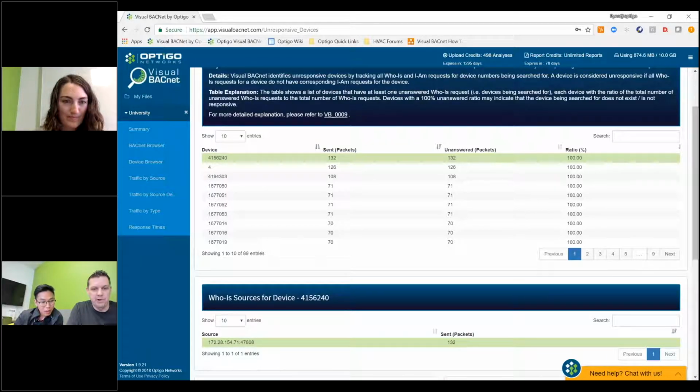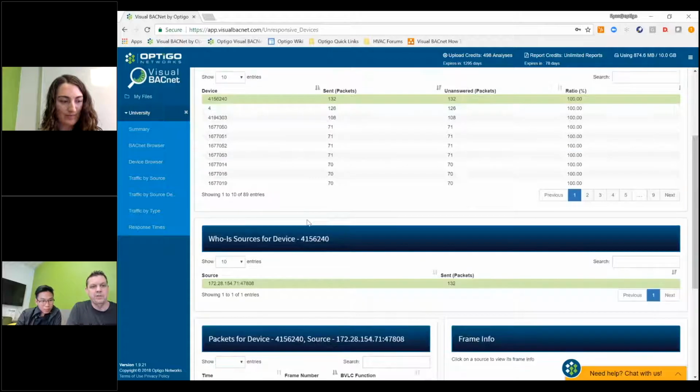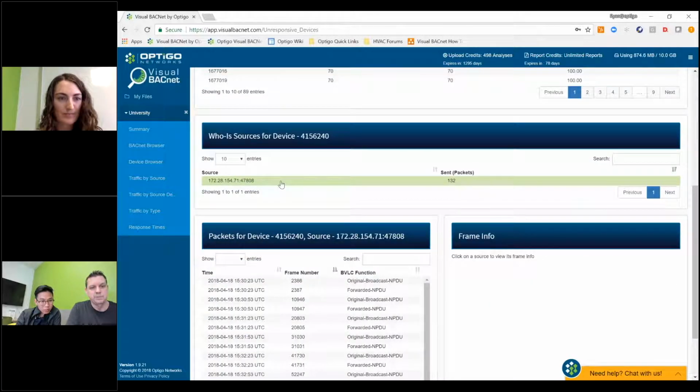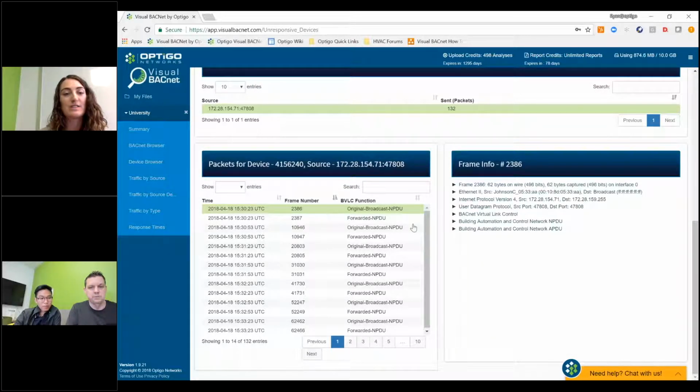So the interesting part about it too is you can actually figure out where it's coming from, right? So when we look at this guy, somebody's looking for it, device is online. But when you click on him, the guy who's looking for it is this guy. So that's easy. At least we narrow it down. I can go straight to the controller and figure out the data exchange on why it's looking for that guy. If it's offline, it should exist. Go to that device, fix it, figure out why it's offline. If that device shouldn't exist, find the source who's talking to it, reconfigure. And that's the same for anything that's offline or unresponsive.